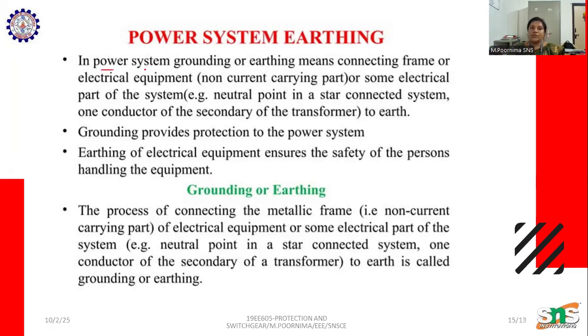So earthing is nothing but power system grounding. Earthing means connecting the frame of electrical equipment, that is a non-current carrying part, or some electrical part of a system, for example the neutral point in a star connected system, or one conductor of the secondary of the transformer, to the earth. So grounding provides protection to the power systems, and earthing of electrical equipment ensures the safety of the persons handling the equipment. So the first thing is the safety of a person who is handling the equipment.